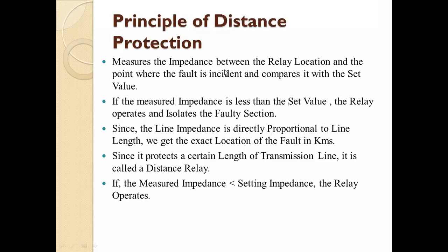When it will operate, we have seen in the last lecture. So when that relay will operate - no, it's not more, because for overcurrent it is different. Overcurrent protection is different and distance protection is different here. Here we are setting the impedance.